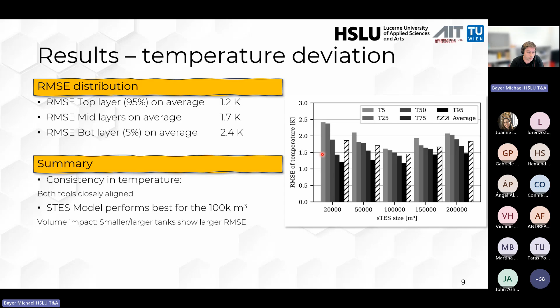But this is also mainly due to temperature evaluation inside the tank. Smaller storages have a higher surface to volume ratio, and in these cases thermal losses are more dominant while stratification is less important. For larger systems, there are stronger thermal gradients and more pronounced stratification, especially near the inlets and the tank bottom.